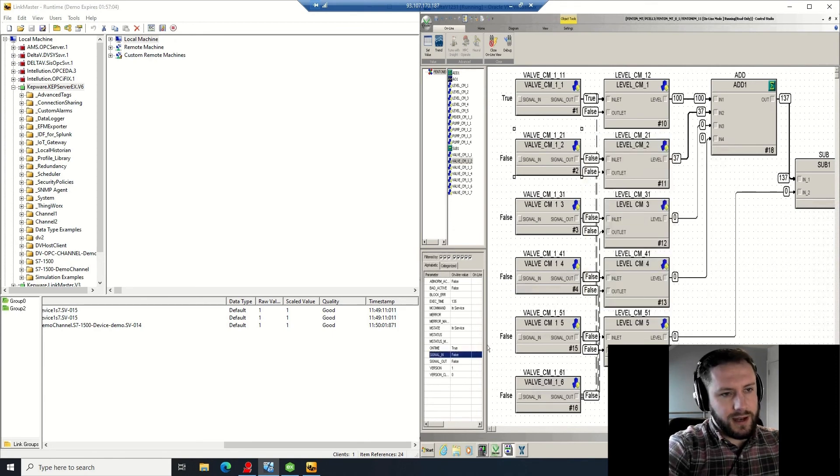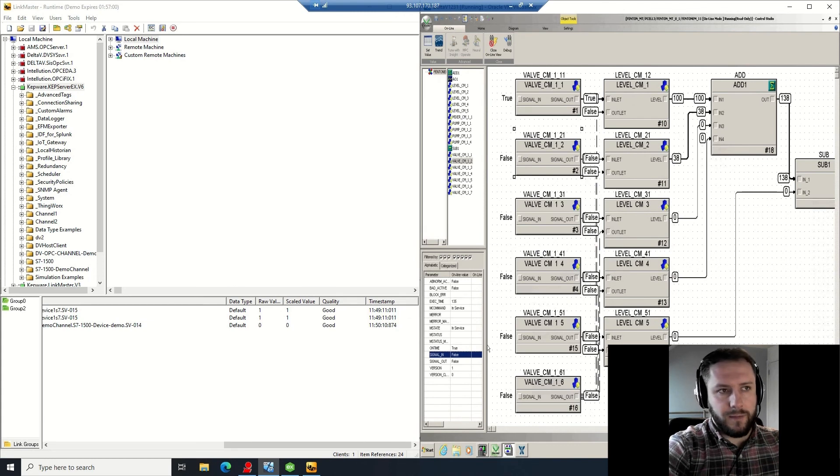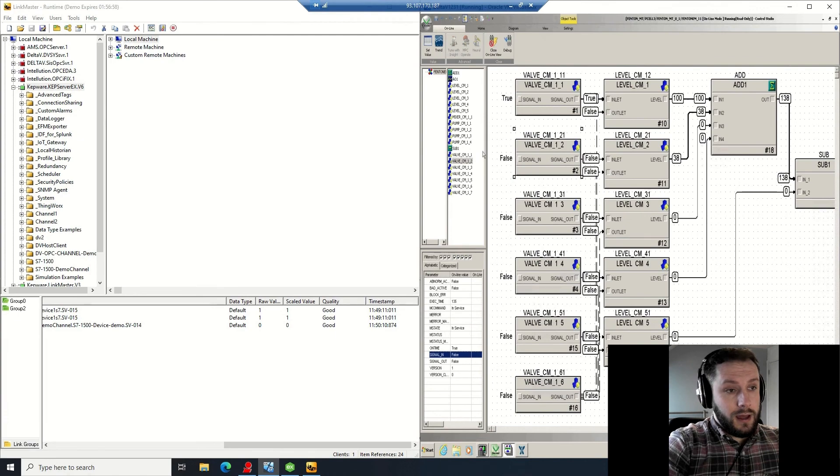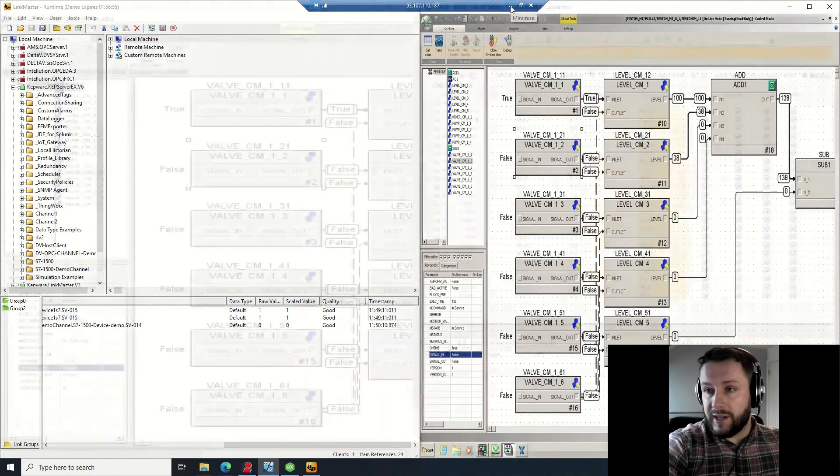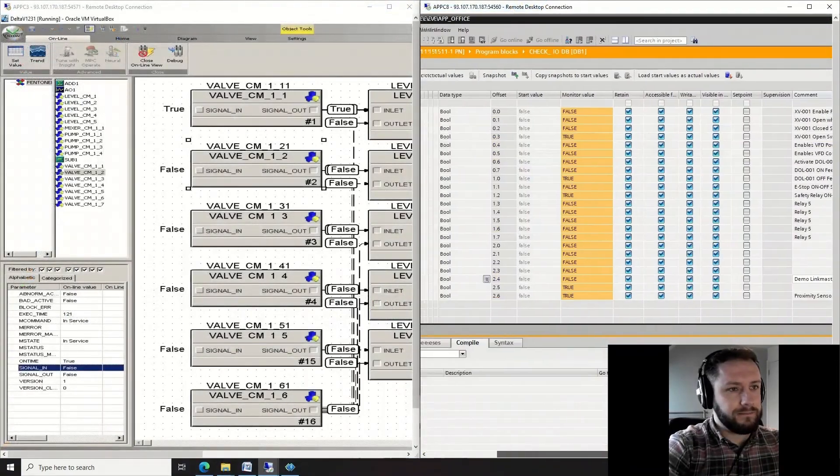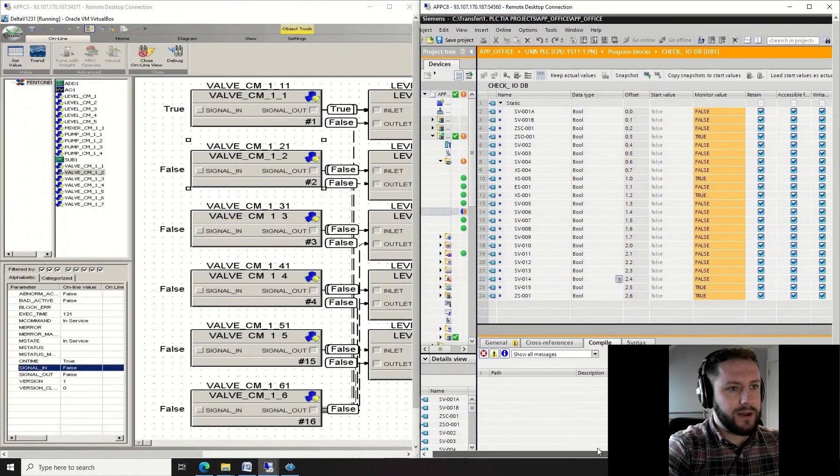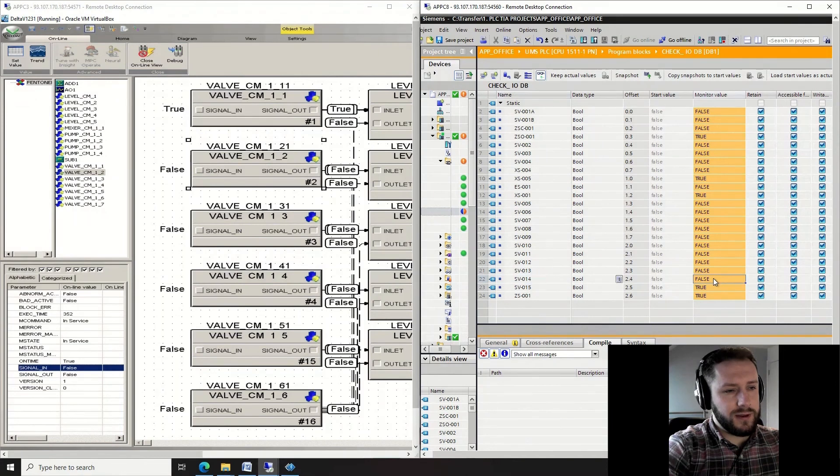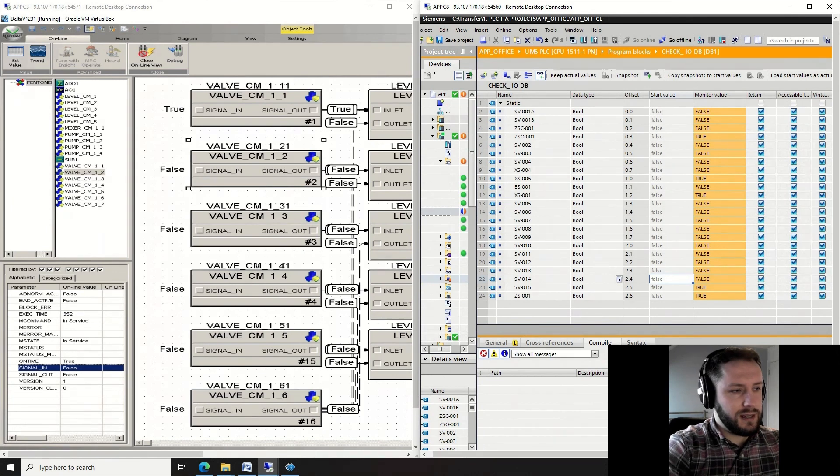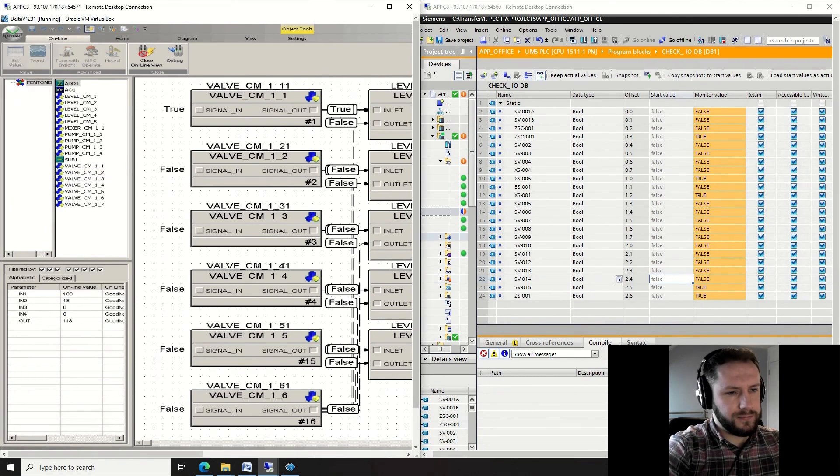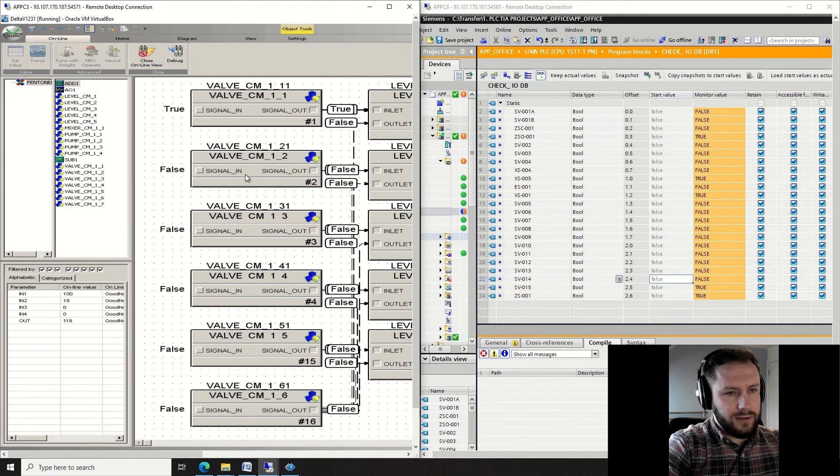And then let's have a look at accessing TIA on the other computer and watch the data block value change real time. All right, so here I have the data block open - SV014, its current value is false. Valve CM signal in value is false. Let's change that to true. Keep an eye on that SV014 value in the monitor in orange.